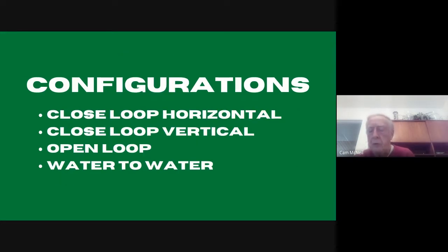Closed loop can store energy for months when heating the building in winter. The ground is cooled, even frozen, giving the advantage of latent heat. When switching to summer cooling, the cold or still frozen ground is heated, making the heat pump more efficient. At the end of the cooling season, the ground has been heated, which makes heating more efficient. Closed loop ground... lake loops can also be used.